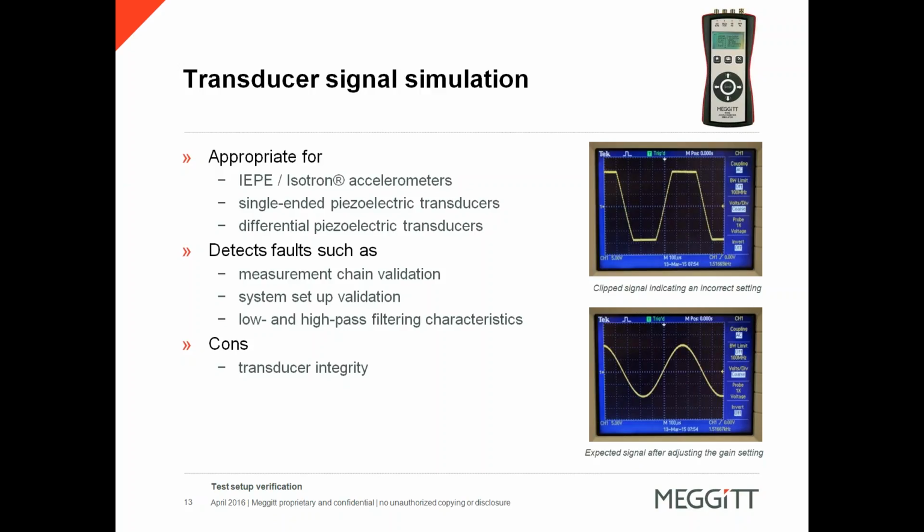We can perform a similar test procedure for charge simulation and insertion in place of piezoelectric accelerometers. Meggitt incorporates this functionality as well in the 4830B for both single-ended and differential piezoelectric accelerometers. This handheld unit simulates the output of a charge mode accelerometer.